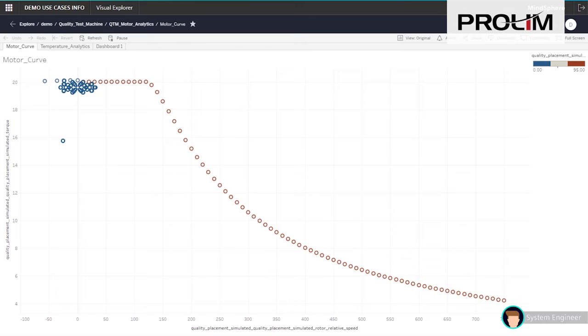By looking at the blue measured data points from the motor, he can see directly that the load is too high for the installed motor and it is operated close to its limits. He needs to make the simulation engineer aware of that problem.